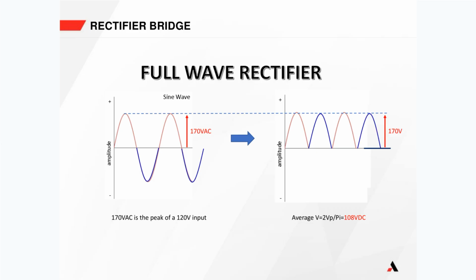We have to keep the output within tight regulation. But the problem is, as a charger manufacturer, we don't know what that AC input is. That AC input is coming from the grid, or from your generation, your turbines on an offshore platform. We don't know if it's going to be exactly, for this example, what comes out of the outlets in your home, 120 volts. It may be 115, it may be 125, we don't know. But if it is exactly 120 volts, the peak of the sine wave will be 170 volts AC.